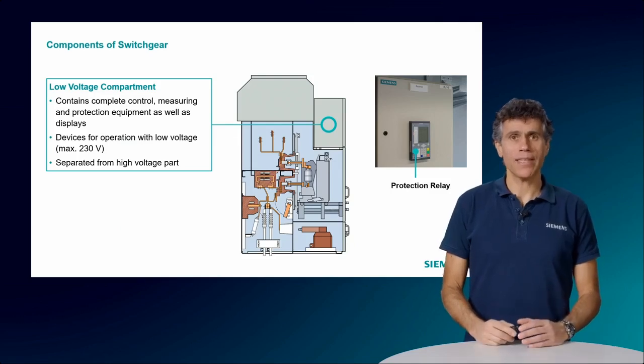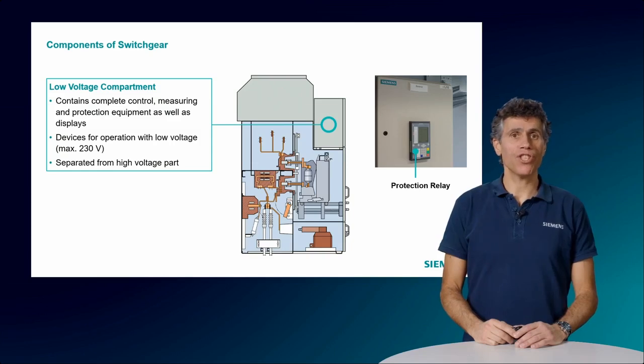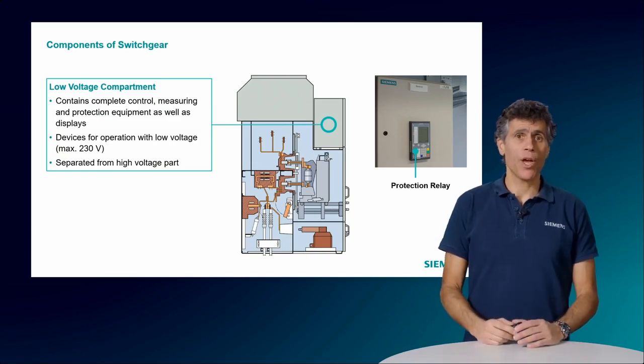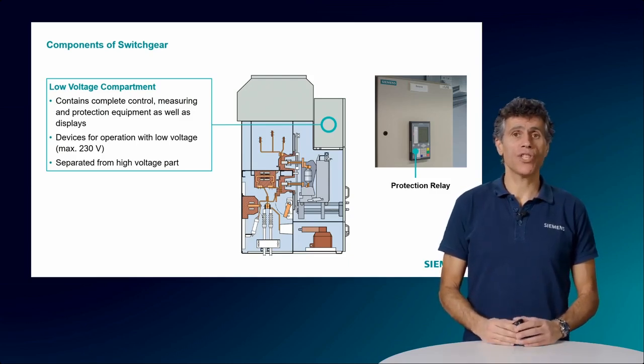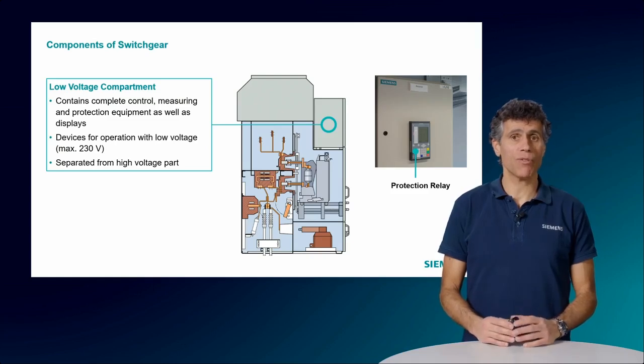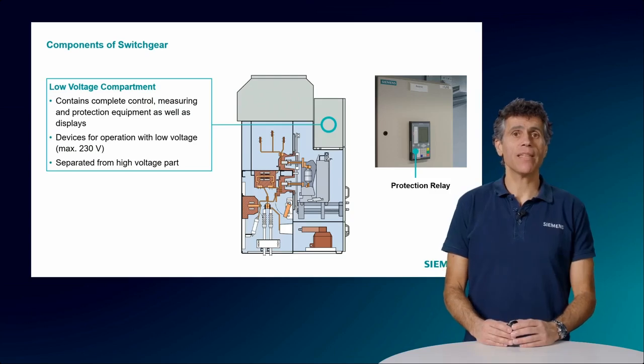The low voltage box, as the name suggests, is a box mounted on the switchgear and fully uncoupled from the high voltage. In this box, we install devices that are used to monitor the condition of a feeder or of an incomer. We may be able to visualize if the earthing switch is connected or not, if there is a faulty condition, we may be able to operate some components electrically, etc. An utmost important device is also installed here, the device that protects the consumer. It's called protection relay, and it's used to decide whether the circuit breaker shall trip, meaning open the contacts, or be kept on. The protection relay is able to do a huge amount of other things beyond its main function.